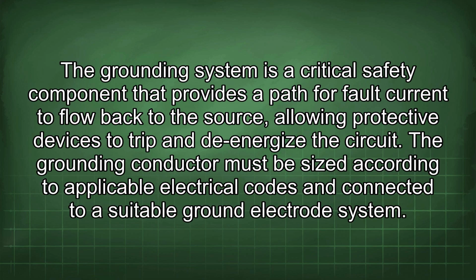The grounding system is a critical safety component that provides a path for fault current to flow back to the source, allowing protective devices to trip and de-energize the circuit. The grounding conductor must be sized according to applicable electrical codes and connected to a suitable ground electrode system.